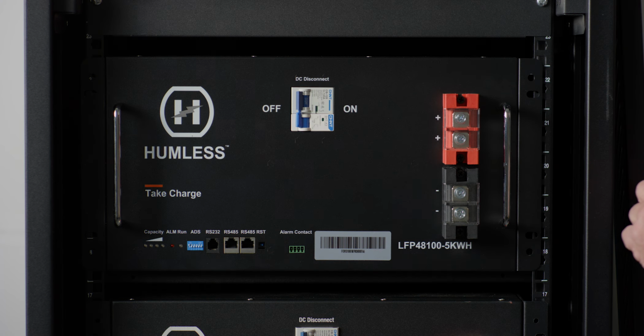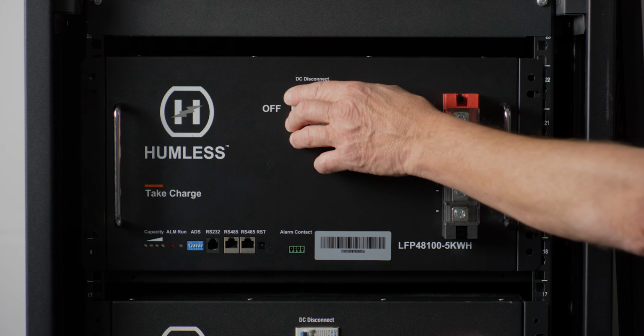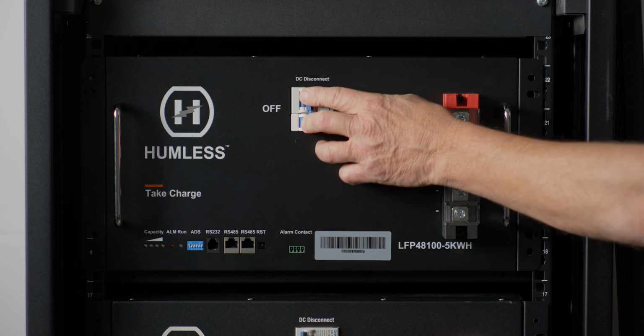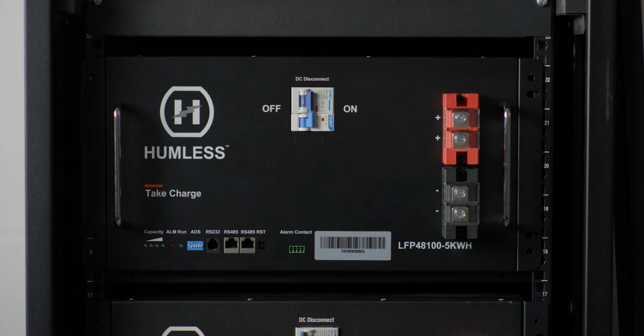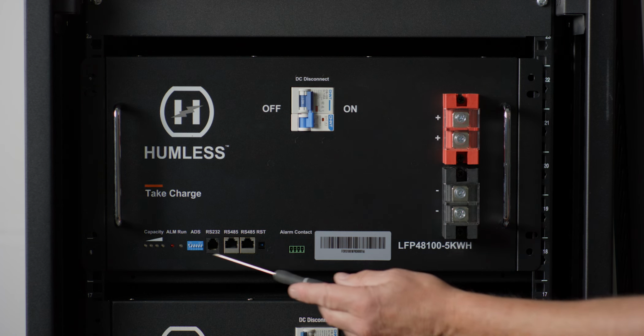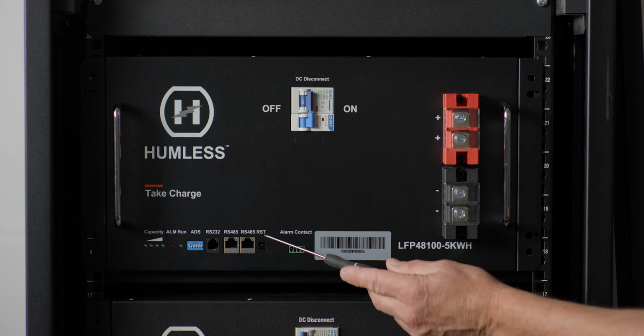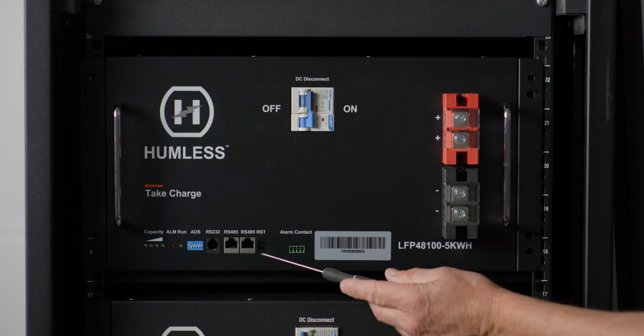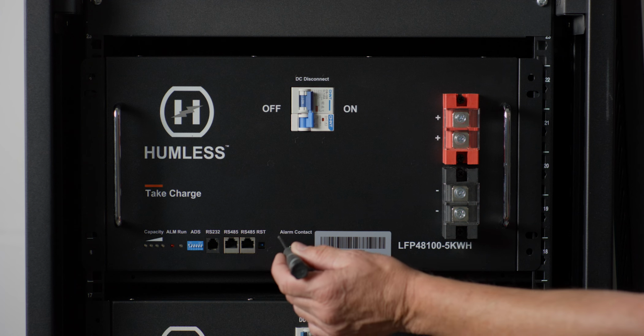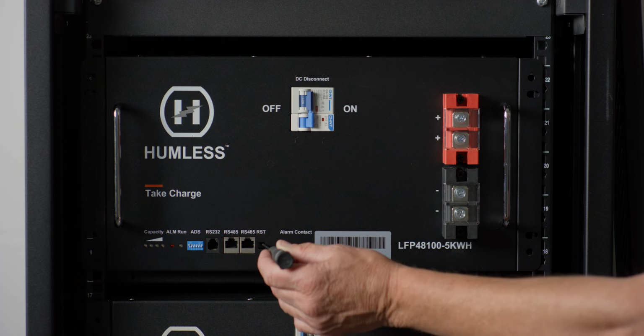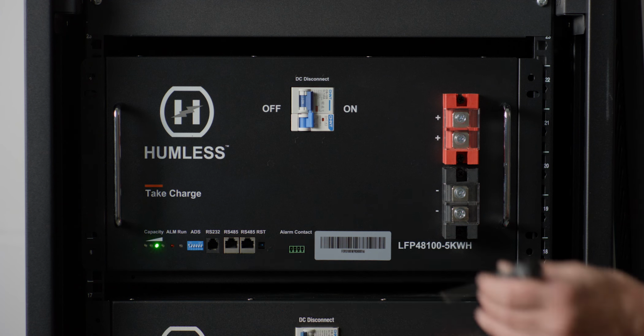To turn on the BMS, first note the breaker located in the center of the battery. The first step is to switch it to the on position. Turning the cell on and off is a simple process using the RST reset button located at the bottom center of the battery. Use a small screwdriver, press and release the button. You will notice the BMS wake up as the indicator lights flash.